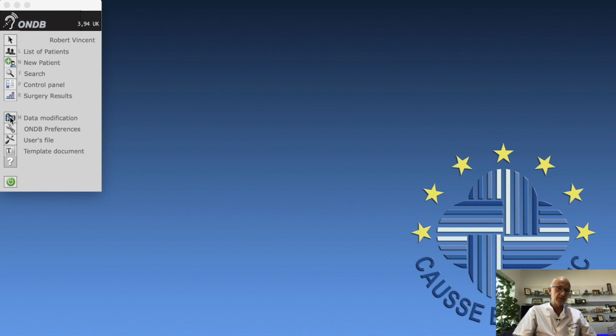In case you make any mistake, for example, by introducing the wrong prosthesis when you enter a patient, and then you discover later on that you entered a wrong prosthesis and you want to change that, everything you've saved in the program is already saved and you cannot change anything, except if you click on a specific area, and then you can change by entering your password, and this will go to this area. This is interesting in case of audit, and you can show that you made some change later on, but not too much.